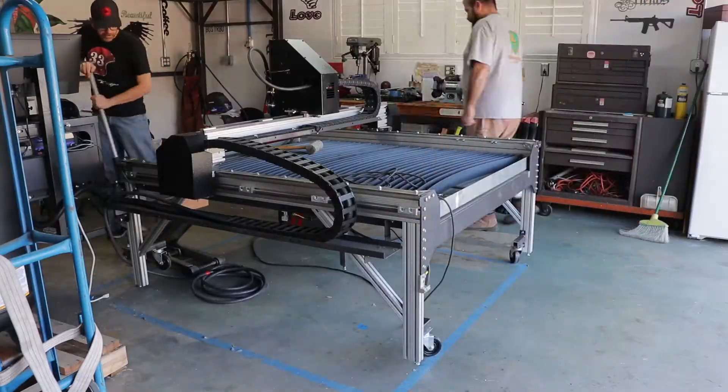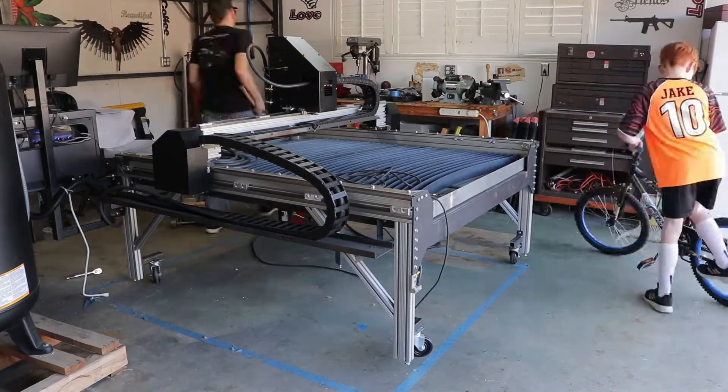So it's been quite a day at Casa Mountain Works — there's been a lot going on this entire weekend. If you remember from the video where I did the electrical, I left a lot of the 240 plugs covered with just a plate on them because I didn't know how we were going to wire them in. We worked on doing that and getting the grounding done. I needed to make an earth ground connection that was close to the table, that was solid, and that was going to introduce as little interference into the cutting process as possible.